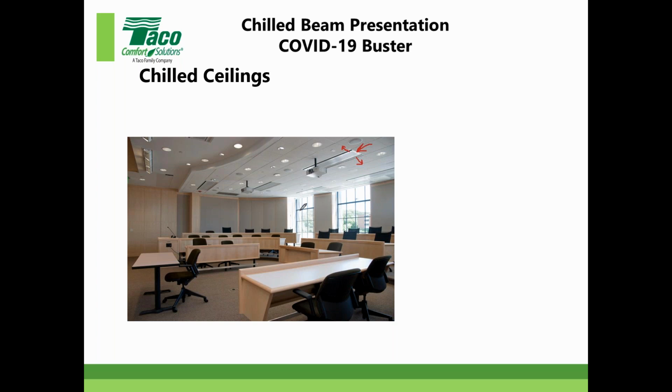We actually shut off the projectors when we're doing a presentation. That's the ceiling mounted projectors, and it takes about 10 seconds for them to cool off and shut off. And then when they do, the space is virtually silent because the system was designed for an NC value of less than 20. We also have in that classroom the radiant panels. That's this guy back here. And what you can't see very well is a perforated ceiling right in the back of the classroom, and that's where our passive chill beams are located. So we have 4 passive, 2 radiant panels, and 9 active chill beams.